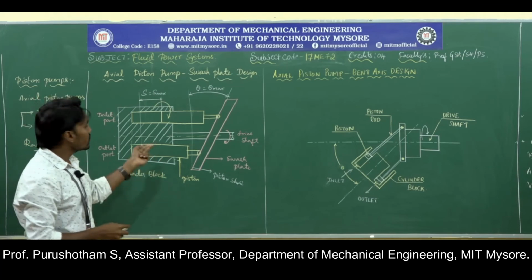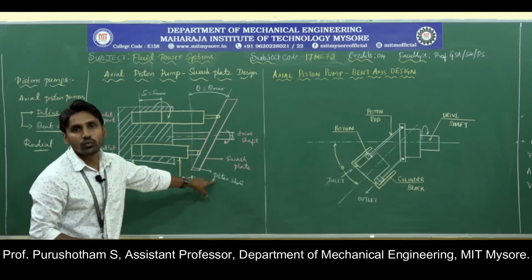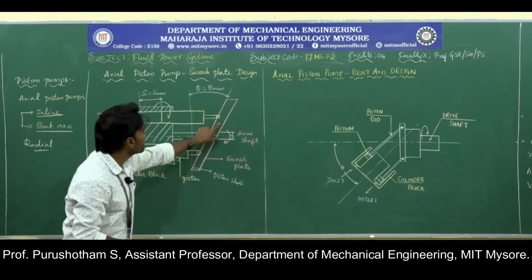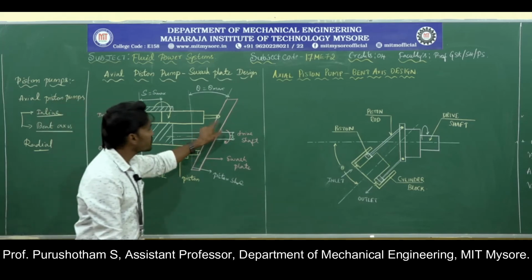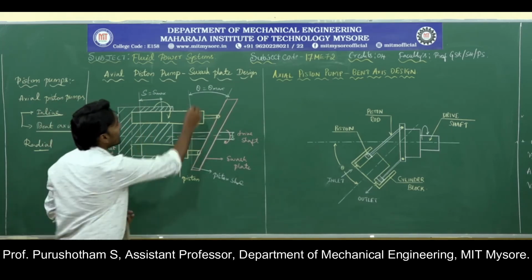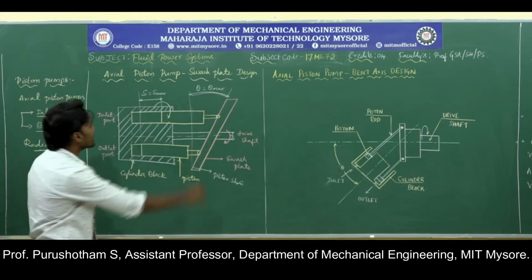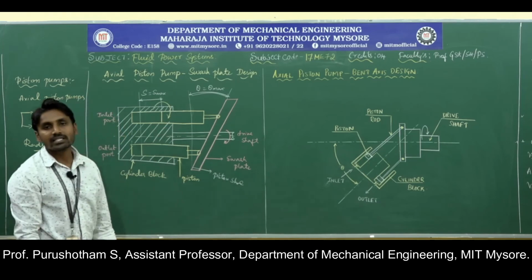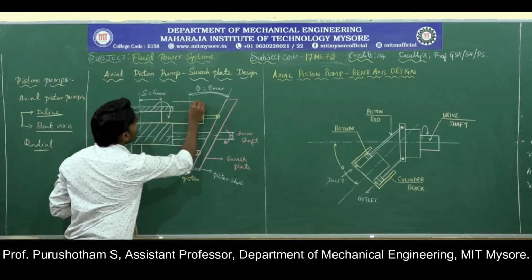that rotation is in turn induced on the piston shoe, so the piston shoe moves on the surface of the swash plate. Since the swash plate is inclined at an angle with respect to the driving shaft or axis of the pistons, this will cause the pistons to move to and fro.